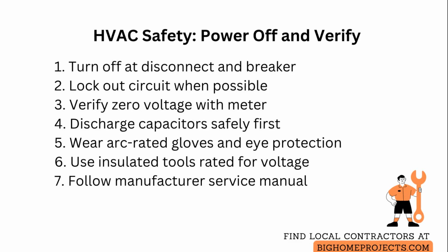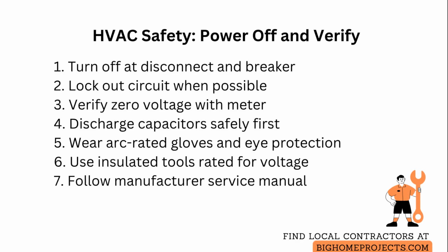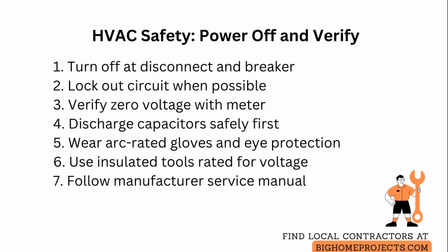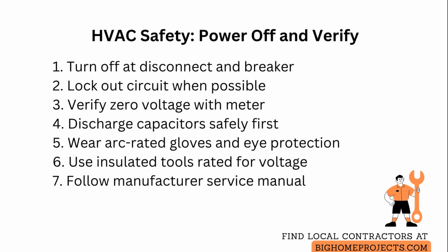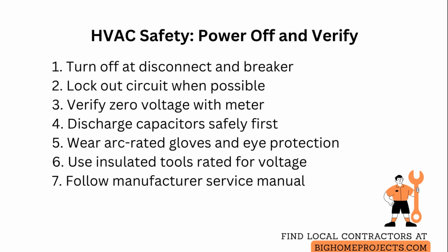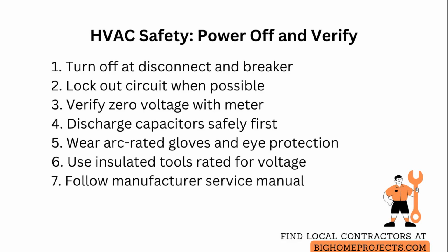Use a properly rated voltage tester or multimeter to confirm there is no voltage present at the terminals and on capacitors, because capacitors can hold a dangerous charge even after power is removed. Wear appropriate personal protective equipment such as safety glasses, arc-rated gloves, and insulated footwear, and choose tools with insulated handles rated for the expected voltage.